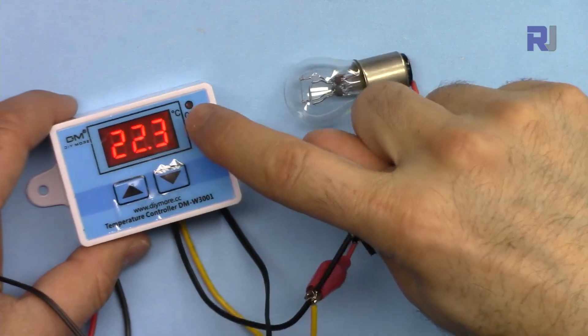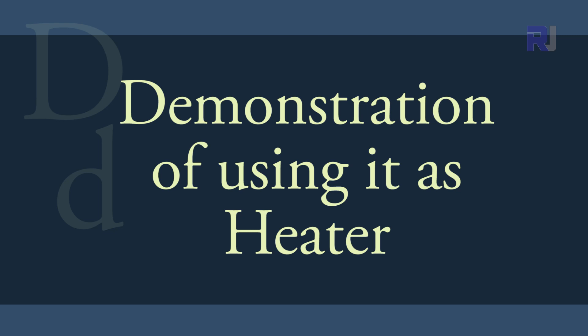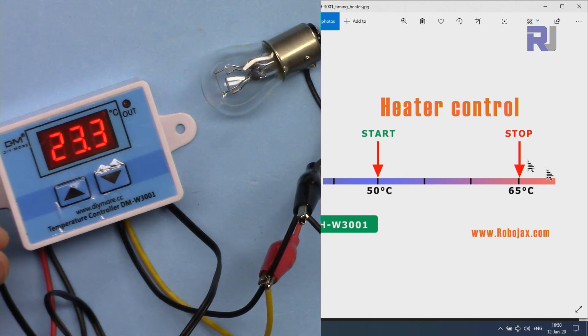Because the output is off the light is also off. Now let me show you how we can use it as a heater or heat control. We have to set our start temperature. For example, if we wanted to keep it between 50 to 65, it means that when the temperature is below 50 it will turn on the heater.